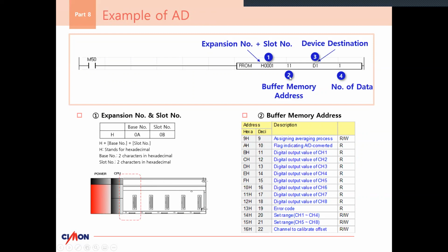When we talk about the buffer memory number 2 component, when you go to the help file, or you should get a list of instructions with each module that you buy, this is the buffer memory address. This is referring to the actual decimal value, not the hexadecimal value. So buffer memory number 11, they're wanting the digital output value of channel 1, and they're going to store that value to device register D1. Remember, that's a word data register, and then it's going to transfer 1 word of data.